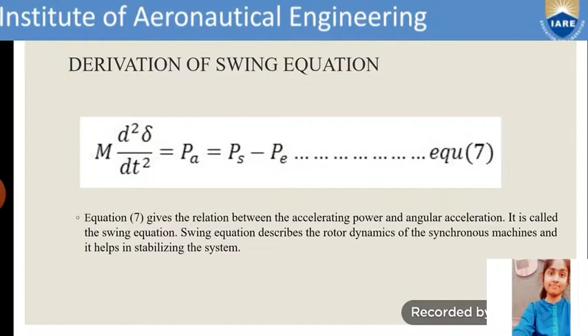Now, let us note that accelerating power in the swing equation will have a sine term. Therefore, the swing equation is a non-linear differential equation, and obtaining its solution is not simple. For a two machine system and one machine connected to an infinite bus bar, it is possible to say whether a system has transient stability or not without solving the swing equation. Such a criterion which decides the stability makes use of equal area and power angle diagram, and hence it is known as equal area criterion. Thus, the principle by which stability under transient conditions is determined without solving the swing equation but makes use of areas in the power angle diagram is called equal area criterion.